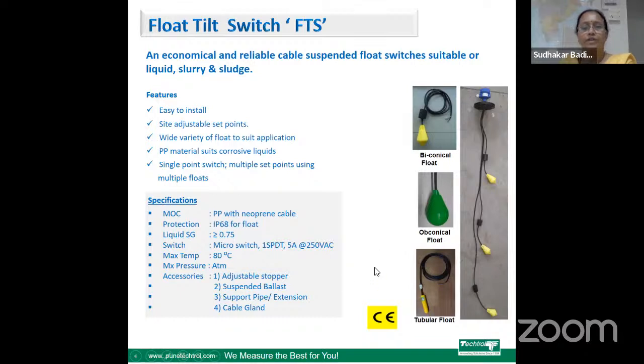So here next one is float tilt switch. This is economical and reliable cable suspended float switch suitable for liquid, slurry and sludge. This is mostly used in wastewater treatment plant. Very easy to install, site adjustable set points, wide variety of floats to suit the applications. So here you can see the switch with biconical shape, then conical shape and tubular float for smaller tanks. The float material is PP, which suits the corrosive liquids. Basically, this is a single point switch and multiple set point using multiple floats is also available.